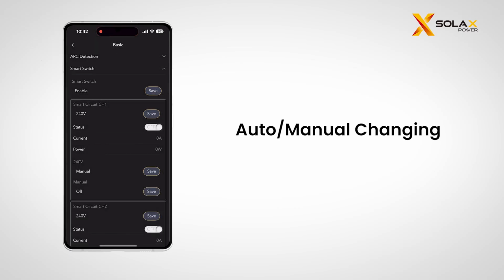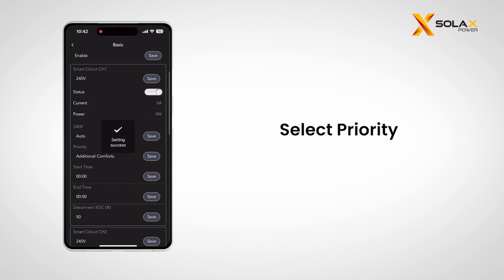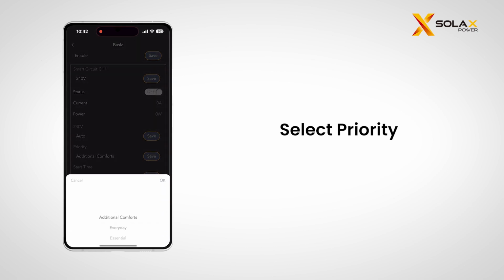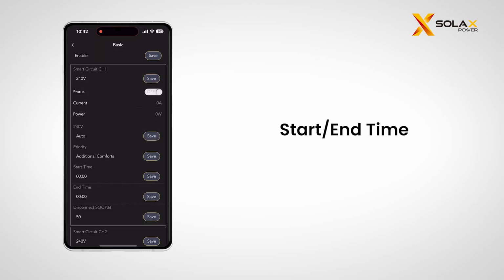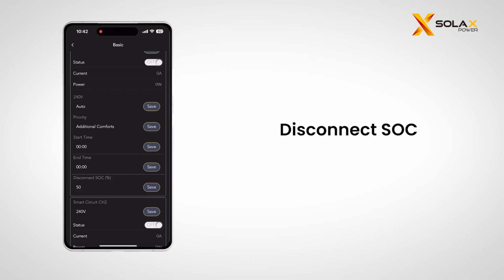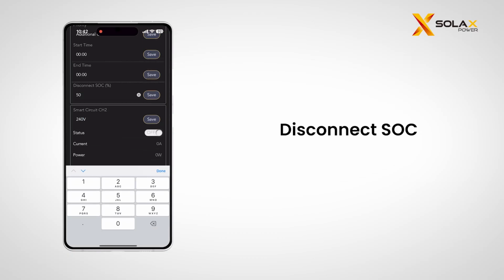Select Priority. Priority 1 Essential. Priority 2 Everyday. Priority 3 Additional Comforts. If you choose the same priority, then it will be in order of CH1, CH2, CH3. Choose start and end time. Choose the disconnect SOC. This function only works when off-grid.